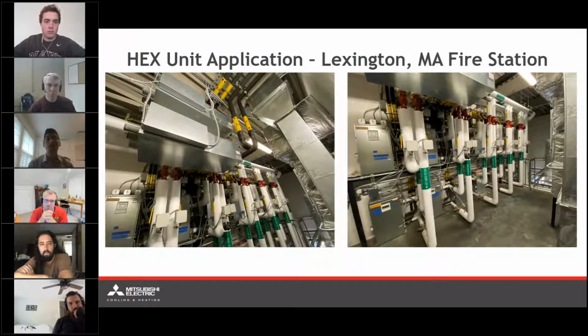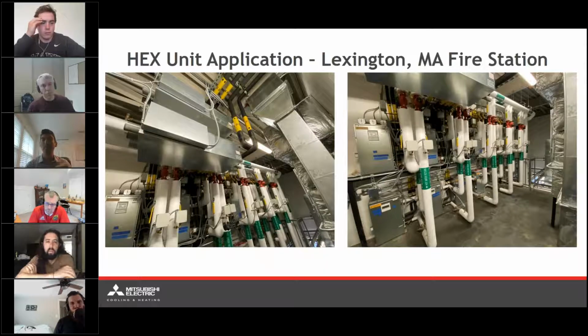And I have a couple pictures here from an installation where we've actually had these HEX units installed. This is located in the Lexington, Massachusetts fire station. On the left, we can see some of the branch circuit controllers above that are ultimately feeding down the refrigerant to these individual units. On the right, we're seeing 1, 2, 3, 4, 5, 6, up to 10. So in this particular instance, we have 10 zones of essentially hydronic loops. These are all HEX aux units, so they're going to be able to provide heating or cooling to whichever water loop is connected. In this instance, this water is used as a hydronic loop throughout the station, and it's able to provide heating and cooling to the space. So this is just an application of how a refrigerant to water heat exchanger can essentially bridge the gap between an existing hydronic loop in a building and a high efficiency heat pump system, a VRF system.